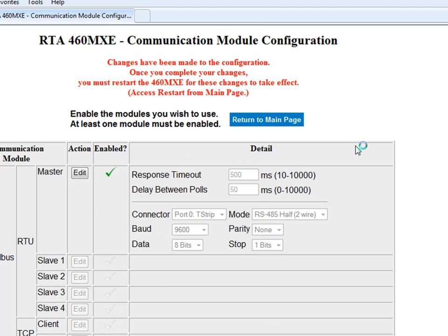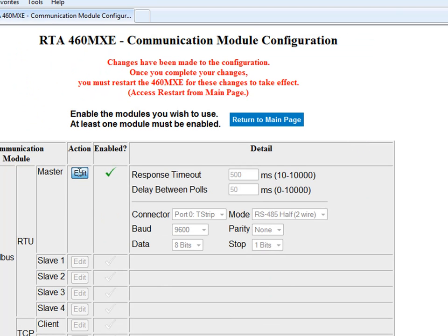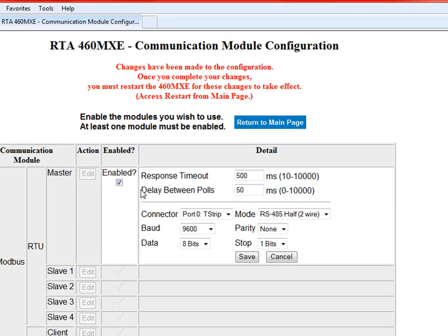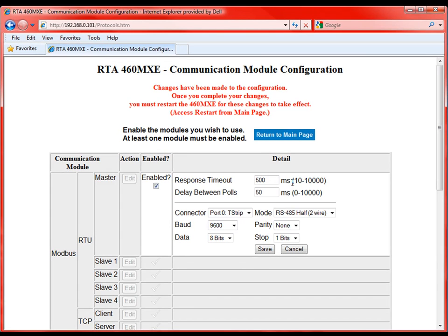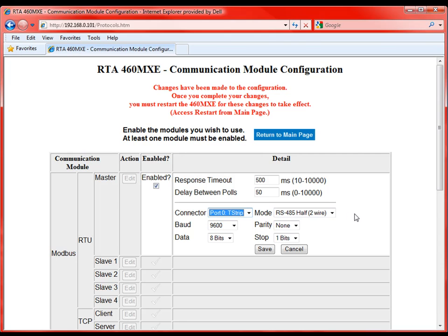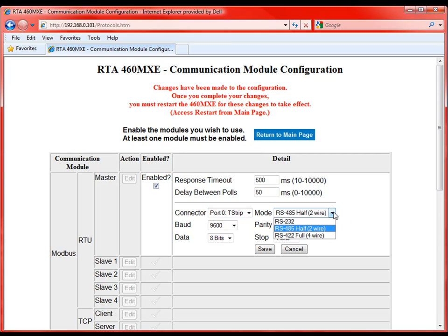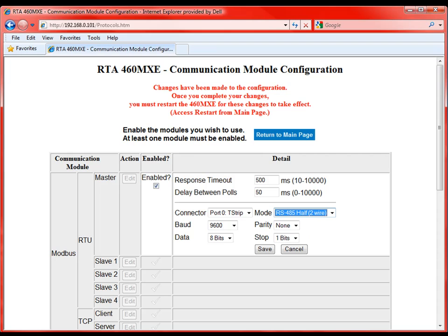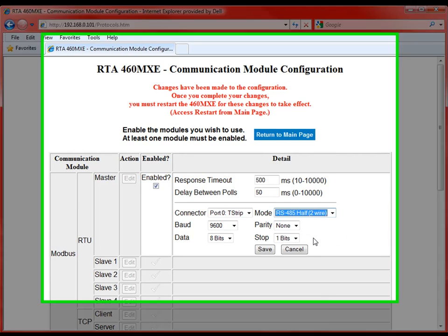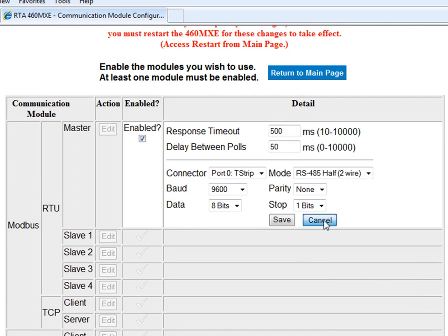So if we go in and edit, there are just a few parameters we'll need to set up in order to get this unit moving. Here, once we go in to edit our Modbus RTU master, we'll see that it's enabled. We're then able to set our response timeout, our delay between pulls, as well as our connection type. This will essentially decide for the unit how often we're going to poll all of the power meters. Out of the box, we're going to have this default to set up on port 0, which is the T-strip on the unit, set up for a 485 twisted pair, essentially two-wire, half-duplex. That is the standard for Modbus RTU. Here you can also define the baud rate, the data parity, and the stop bits.